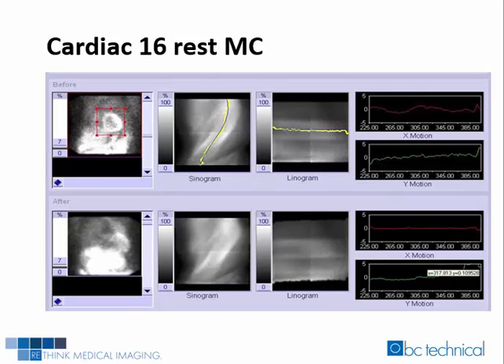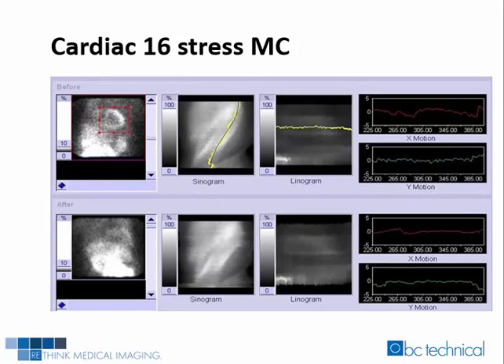Cardiac XVI's resting study showed around three pixels of motion. The motion-corrected dataset exaggerated the motion and displayed over five pixels of motion after automatic motion correction was applied — increasing the motion from three to five pixels. Cardiac XVI's stress study showed around two pixels of motion. After automatic motion correction was applied, the corrected dataset still displayed two to three pixels of motion, showing more motion than the non-corrected dataset.